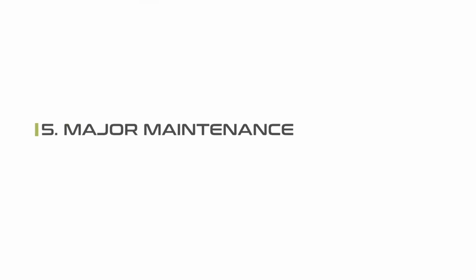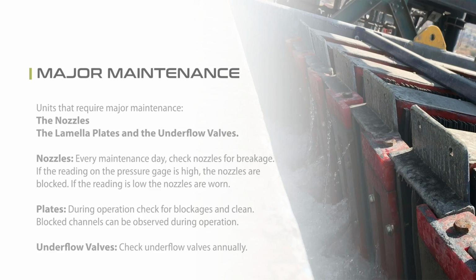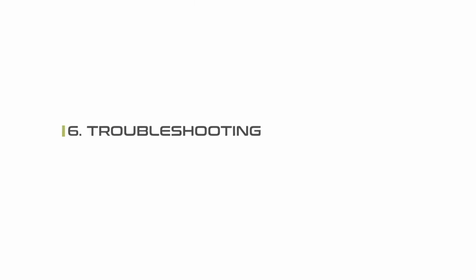Major maintenance. Units that require major maintenance include the nozzles, the lamellar plates, and the underflow valves. Every maintenance day, check nozzles for breakage. If the reading on the pressure gauge is high, the nozzles are blocked. If the reading is low, the nozzles are worn. During operation, check for blockages and clean. Blocked channels can be observed during operation. Check underflow valves annually.